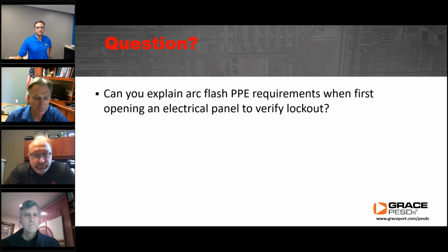So the first thing here is to understand what the work task is, and if the work task is opening a hinge door, then that is an identified work task in Table 130.5(C) or table 2 in Z462. And if you look at that table, depending on condition of maintenance, it does say that the likely occurrence of an arcing fault occurring is yes. So in that circumstance, you would be required to complete an arc flash risk assessment to define the PPE that you would need to open the hinge door.